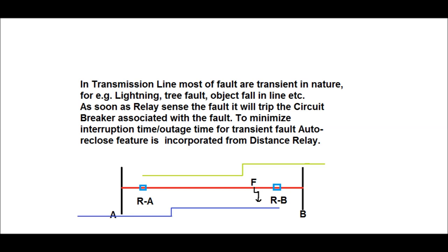That is, when the relay senses the fault, particularly of that phase, it will send a trip signal for that phase of the circuit breaker. Therefore, if there are separate poles of the circuit breaker, it will trip only the faulty phase of the circuit breaker. After a certain dead time, the distance relay will send a closing pulse and close the circuit breaker to normalize the feeder. Therefore, the autoreclose feature is used to minimize the outage time or interruption time and to maintain the steady state power supply.